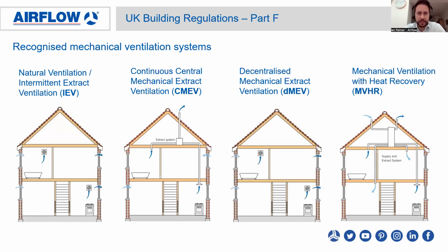Some of the recognized ventilation systems that Part F refers to include natural ventilation with intermittent extract ventilation, or IEV, continuous central mechanical extract ventilation, or CMEV, decentralized mechanical extract ventilation, DMEV, and mechanical ventilation with heat recovery, MVHR. With IEV, as in the image there, you've got intermittent extract fans in the wet rooms, and then you have the natural ventilation coming in through the windows or through the trickle vents. With continuous central mechanical extract ventilation, you would have a single extract unit shown there in the loft space, extracting again from the wet rooms, and then you've got natural window ventilation for the supply.